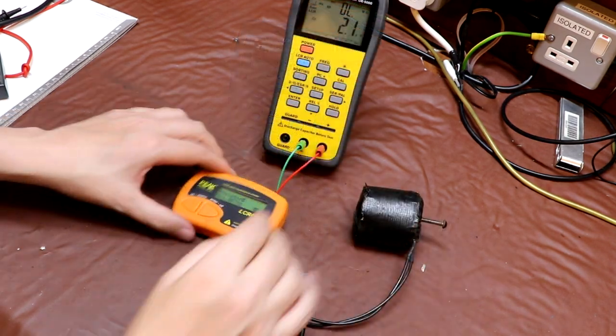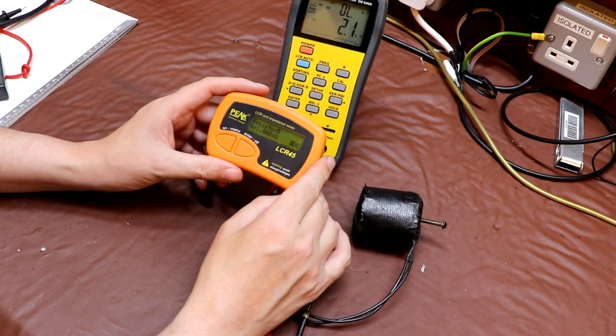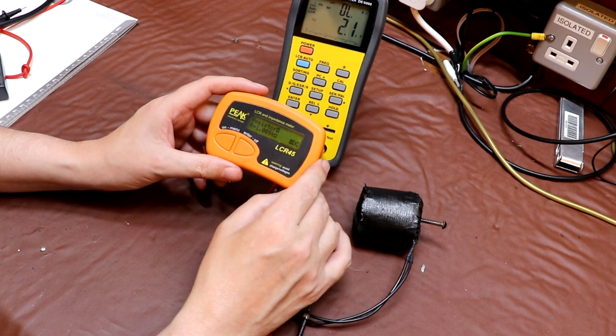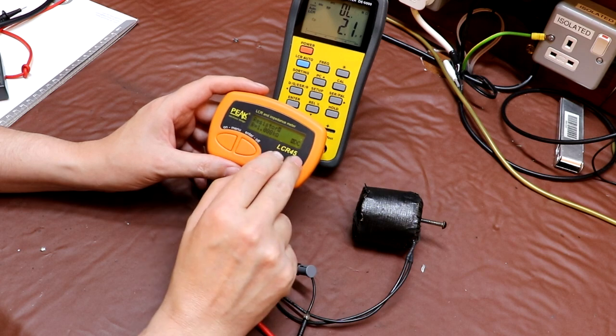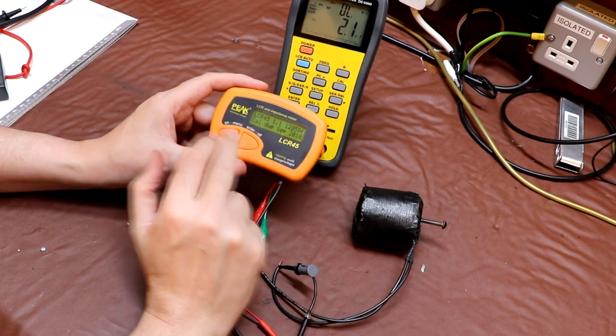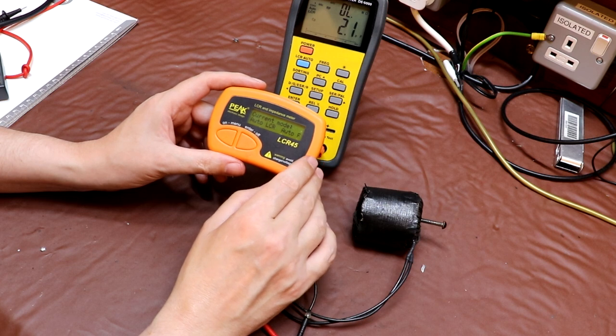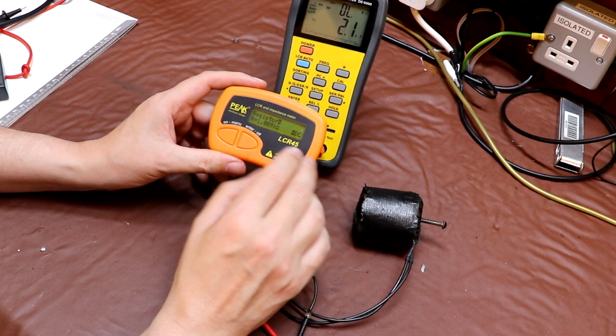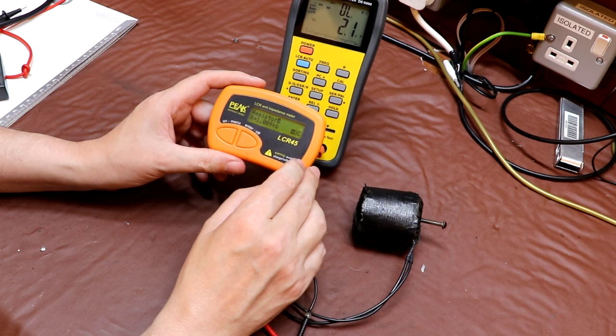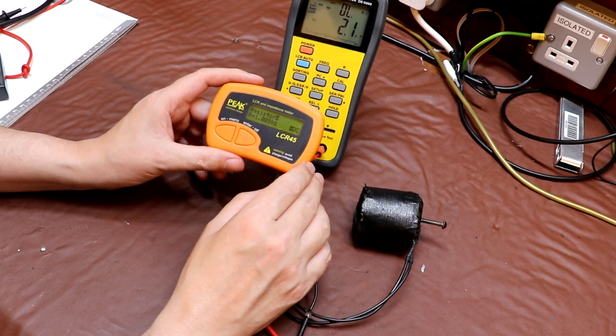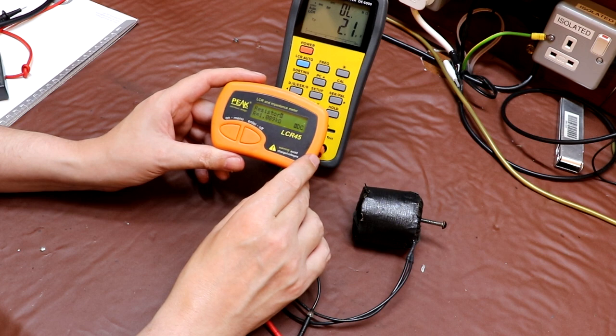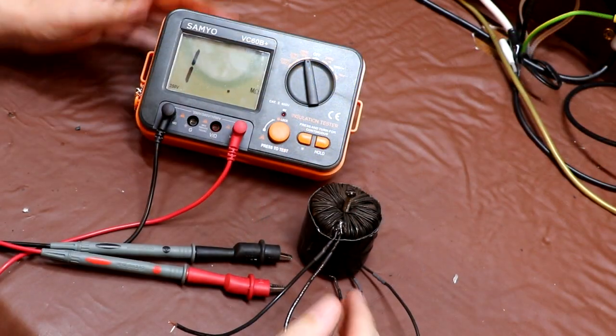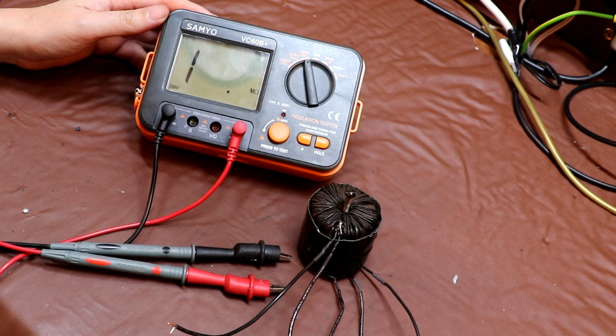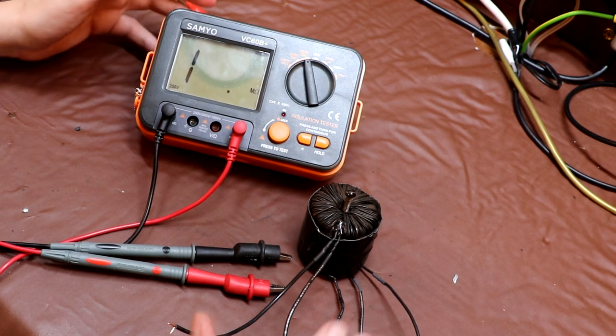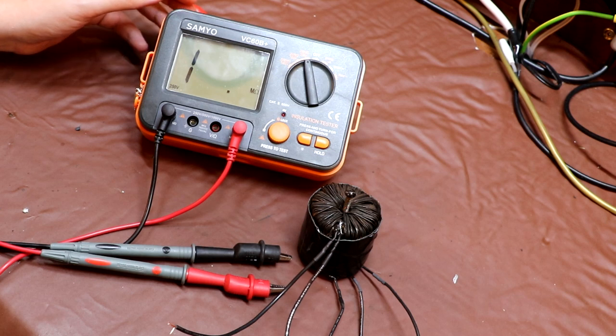Now strangely enough, if I take the Peak LCR meter, I get a different reading, or in fact no reading at all for inductance. It thinks that this is a resistor of about 1 kilo ohm. So I'm not exactly sure why the Peak LCR 45 doesn't measure that. Maybe it's outside its inductance range. I don't know what the specification is, but certainly it doesn't want to read the inductance. Off camera I've already done an insulation resistance test on our transformer here, but I know you guys feel a little bit short-changed if you miss anything, so we're going to do that again.